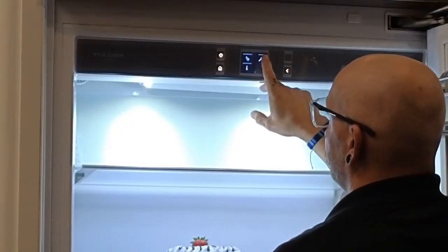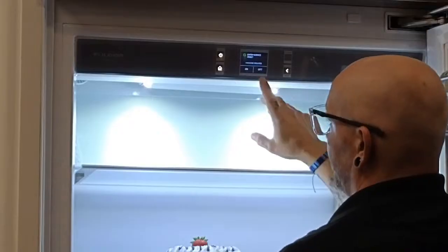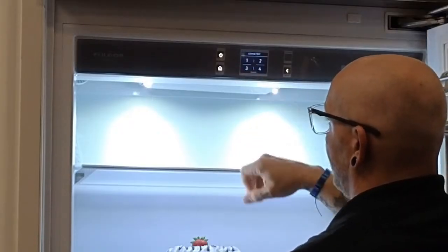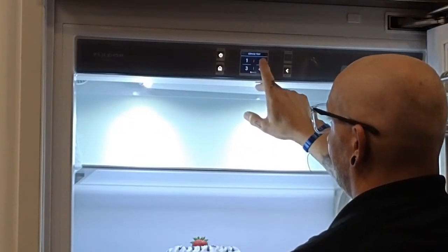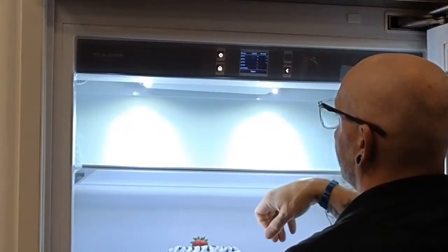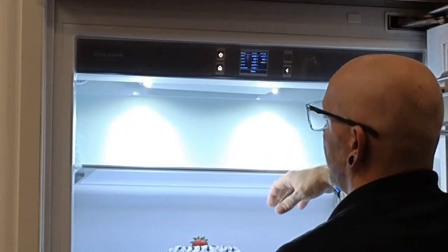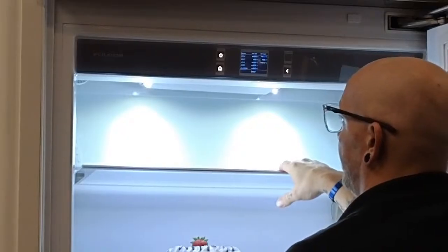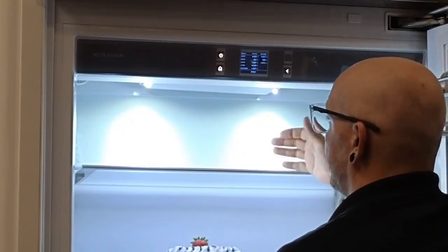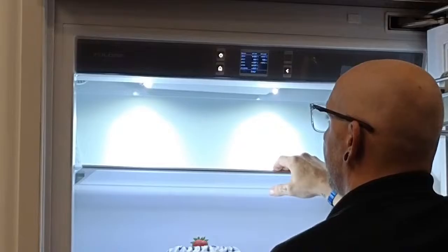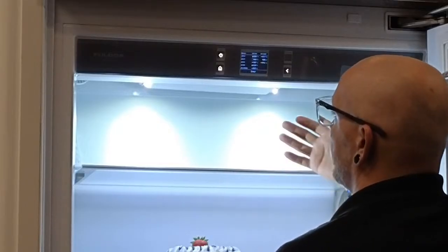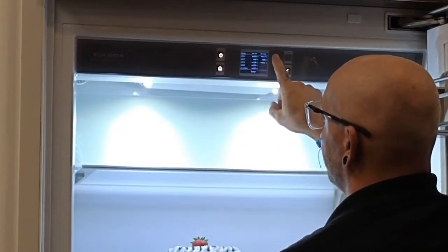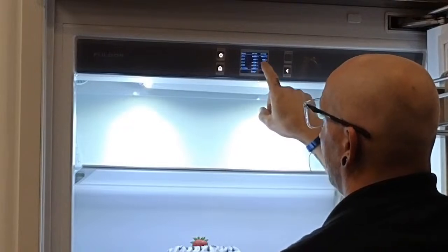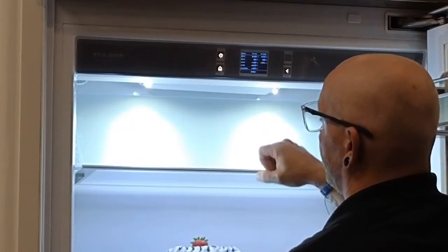So let's go ahead and push the service button. There's also a super secret code for getting into service mode. First step of service mode is going to be your temp probe readout. So during this temp probe readout, it is unfortunately all in Celsius and you have to do some conversion, but this tells us a lot of information. We've got air sensors, evap sensors, we've got your condenser sensor and your ice maker sensor.